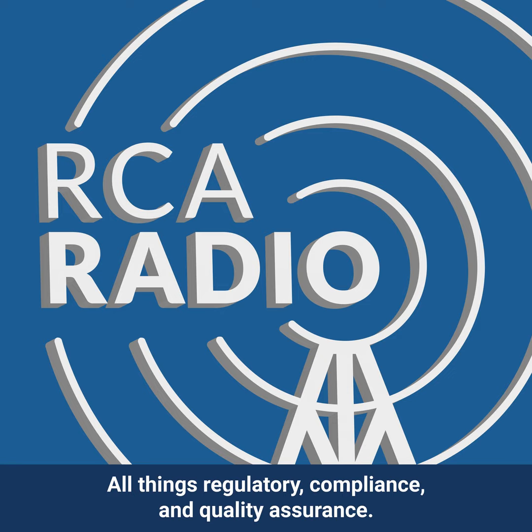All right. So now that we've got the basics out of the way for our listeners, why should companies take design controls seriously? Well, besides the fact that they're required by regulators and regulatory agencies, it is a methodical approach to medical device development that outlines how the product gets created, how it gets tested, how we know that we're creating something that the users want and need, and it connects all the way through.